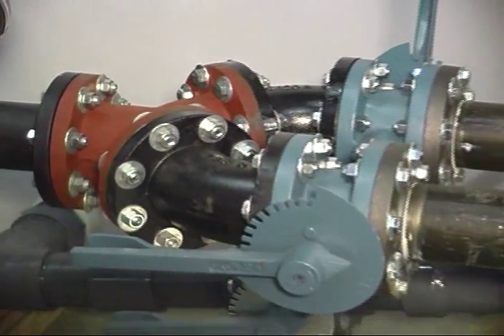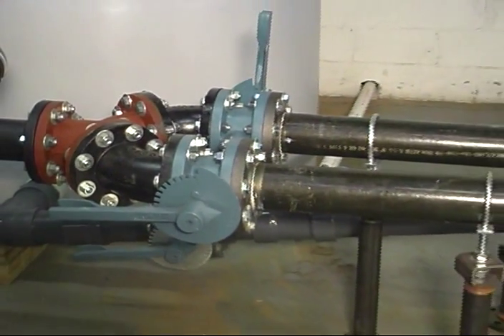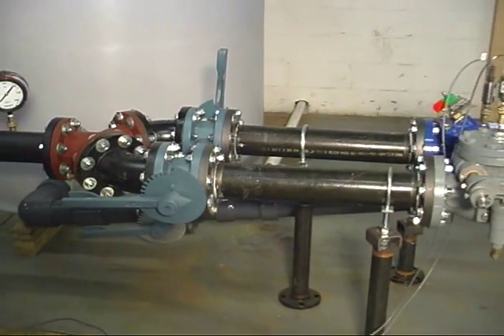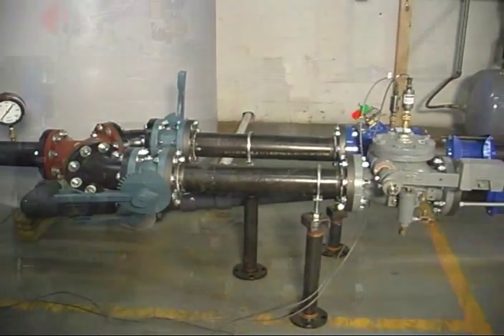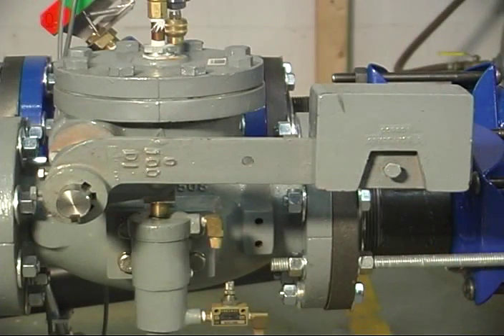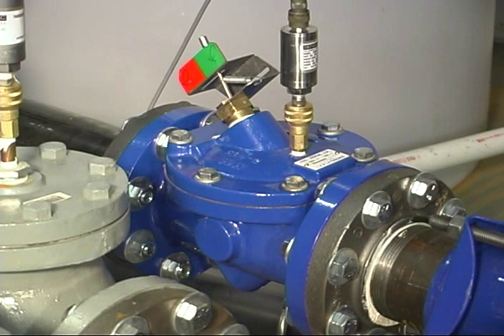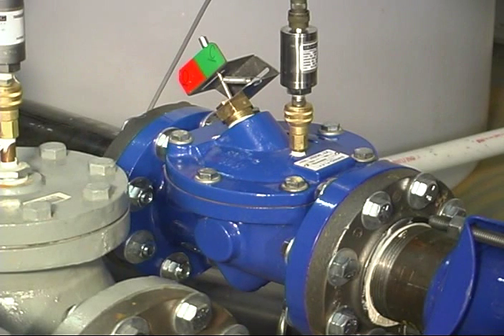Today we have the flow loop configured to do side-by-side check valve testing, dynamic testing, where we slam the check valves closed. We have a cushion swing check valve and a surge buster check valve side-by-side in the same kind of configuration.